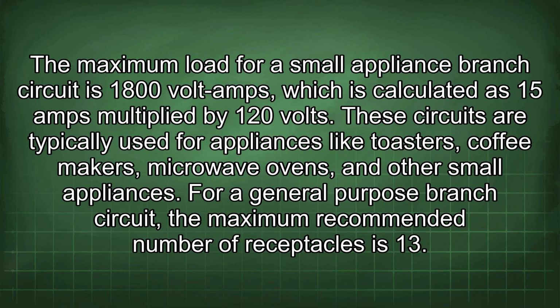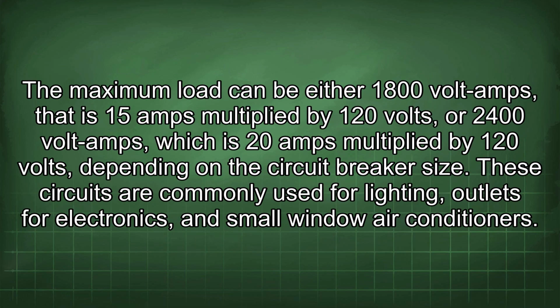For a general-purpose branch circuit, the maximum recommended number of receptacles is 13. The maximum load can be either 1800 volt amps, that is 15 amps multiplied by 120 volts, or 2400 volt amps, which is 20 amps multiplied by 120 volts, depending on the circuit breaker size. These circuits are commonly used for lighting, outlets for electronics, and small window air conditioners.